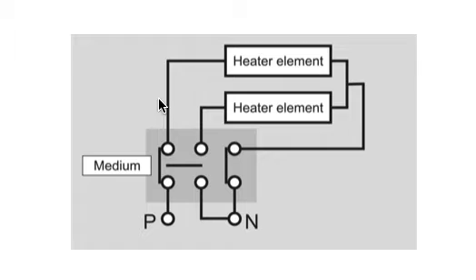So through the phase, to the element, back through the neutral. So this is the medium position. The resistance is half that of the first position. We'll get more current flow and we'll get more heat than the two in series.